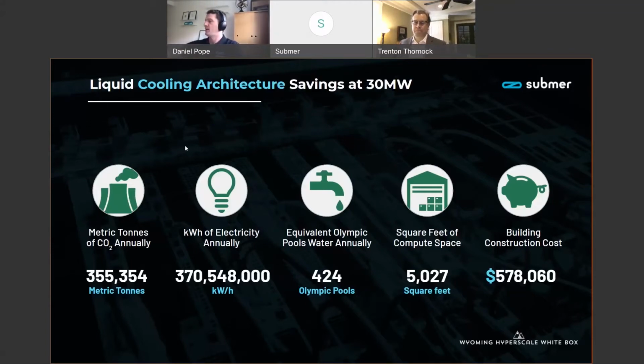How would that compare typically to a traditional build, Trenton? This is just the compute space and doesn't include all of the space required around it to navigate, so the savings will actually be larger than this. When we originally started this project, our assumption was that we'd need at least a 350,000 square foot building, along with all the backup generation, warehouse, and network operations center. That has already shrunk by more than a third, and I think by the time the final design is polished off it will be even smaller. So we're seeing significant savings based on our selection of cooling technologies.